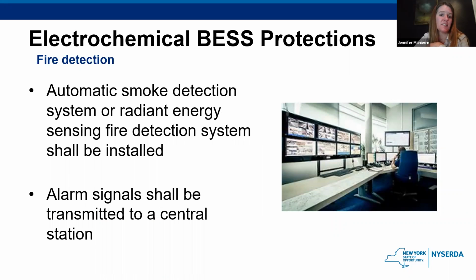Okay, fire detection. There needs to be some sort of automatic smoke detection. If that's not possible, maybe it's an open air area and you wouldn't be able to have the smoke build up enough. You can have some sort of radiant energy sensing or heat sensor for the fire detection system. So one or the other there. And all alarm signals need to be transmitted to a central station. Those central stations are used to monitor the fire alarms and make notifications to the fire department if they need to, if a signal is going off and something's wrong. And for the most part, those central stations are going to be located off-site somewhere and monitored remotely.